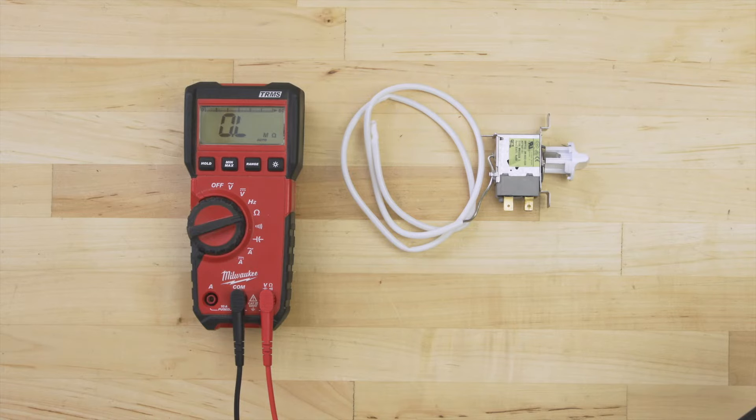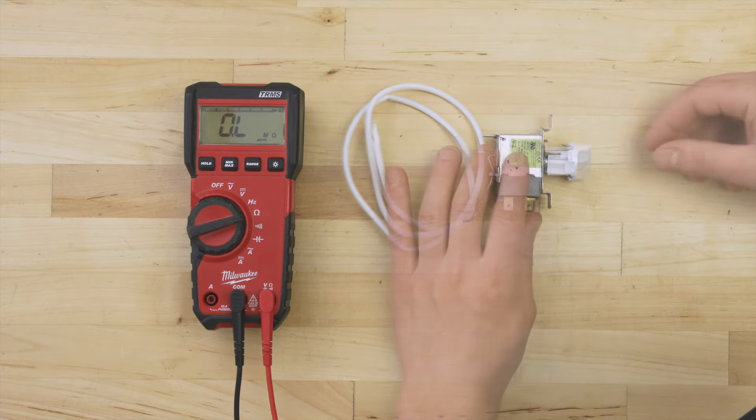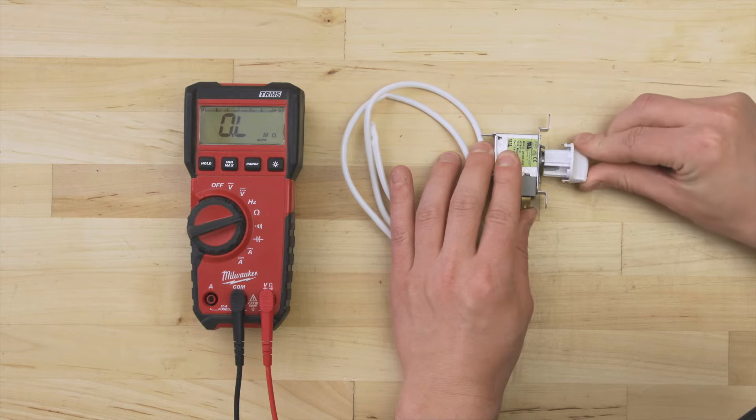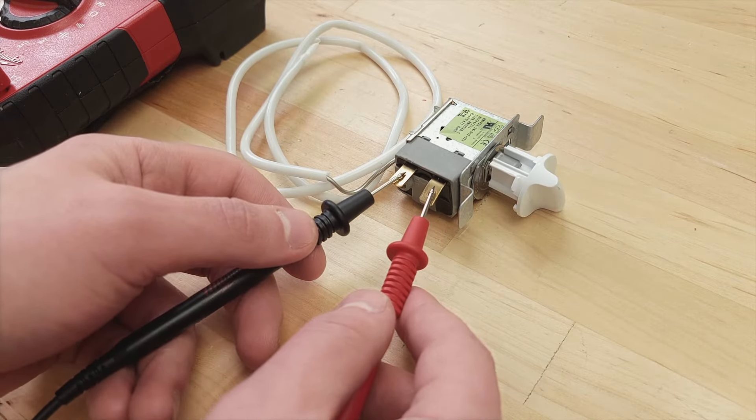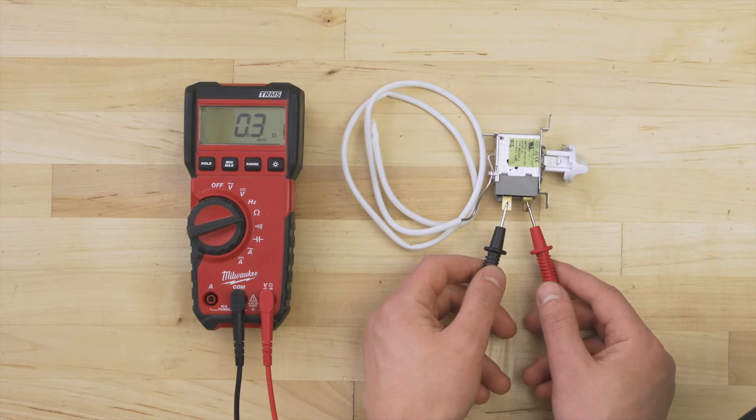Set the multimeter to the ohms or resistance setting. With the dial turned to any cold setting, test between both terminals. You should get a continuity reading between 0 and 1 ohm at room temperature.